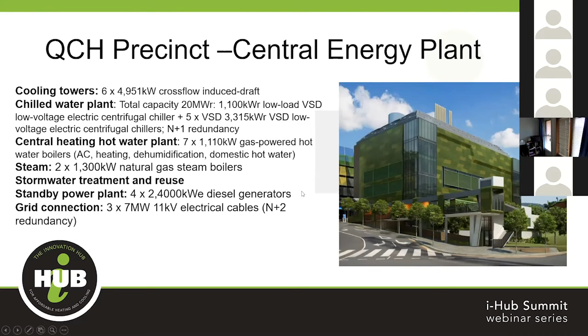It also has about 7 gas water heaters, and they're looking at replacing 1 or 2 with electric or dual-fuel boilers to improve reliability. There are also 2 natural gas boilers to make steam, plus stormwater treatment reuse, standby power plants, and grid connection—3 sources in total. It's kind of an N+2 redundancy: if we have 2 out, it's still okay for the whole site.